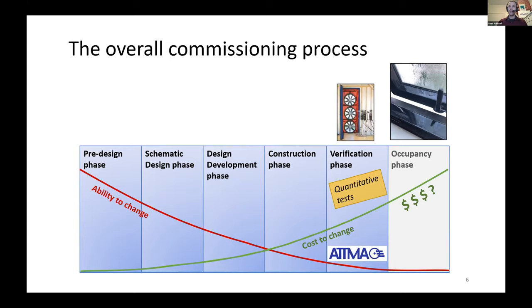So the blower door test is really done at the very end of the project. That's where, if you've done a good job, it amounts to a good pat on the back to say, good job, we really did this well. That's what a blower door test at the end is. And it's a quantitative test. It's a number that you can then report to ATTMA, to the database that ATTMA runs.